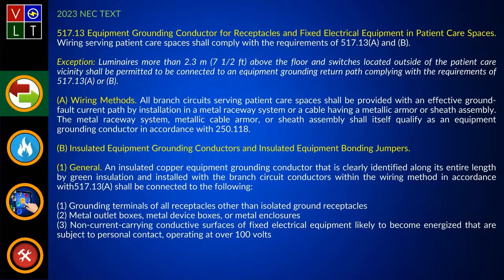Yeah, I know what this is about, and I remember back when I was an apprentice and we started using BX cable, or AC cable, whatever you want to call it. We were always told to wrap it back, but there was really nothing in the code that addressed it. I remember when they were discussing this, because we had done a publication on AFC cable, just the installation of AFC cable. At that time they were discussing this particular myth of the week, and they started writing 517.13, making changes to it. When you look at this section, it refers you to 250.118, where you're dealing with the metallic cable armor or the sheath assembly itself.